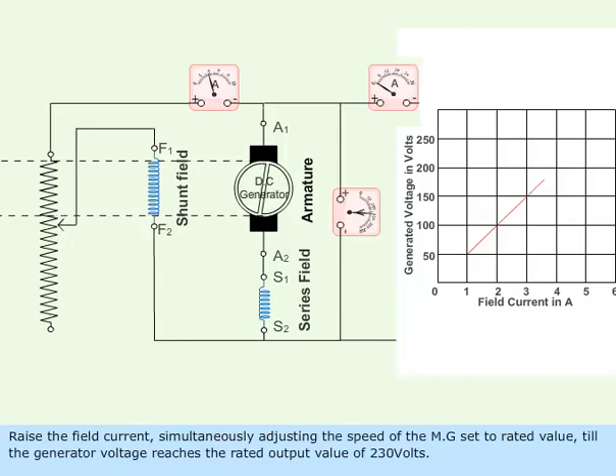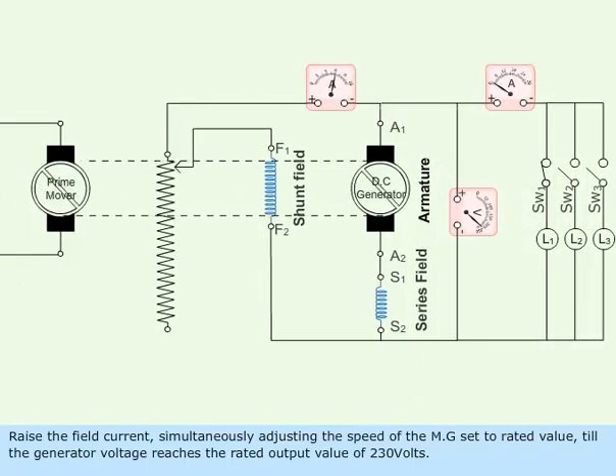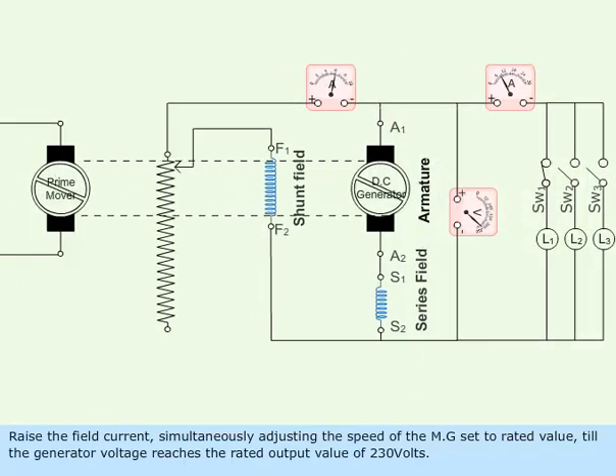Raise the field current, simultaneously adjusting the speed of the MG set to rated value till the generator voltage reaches the rated output value of 230 volts.